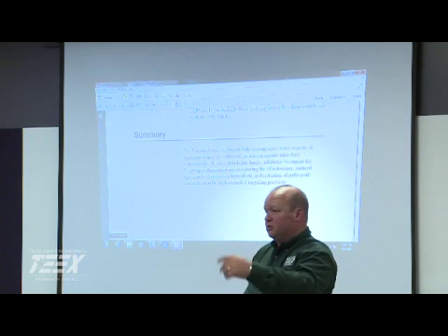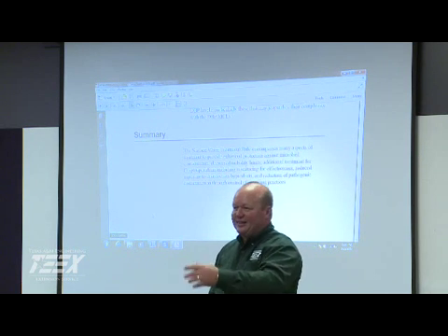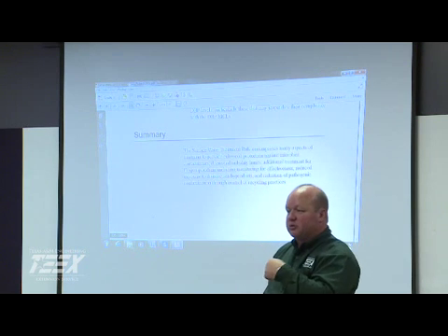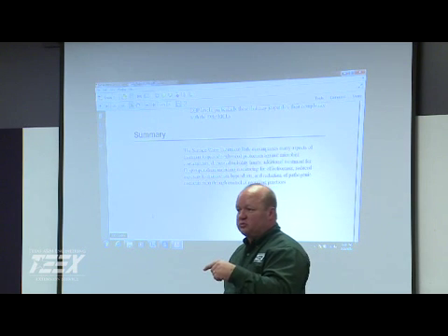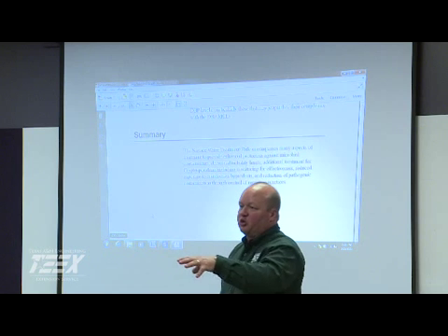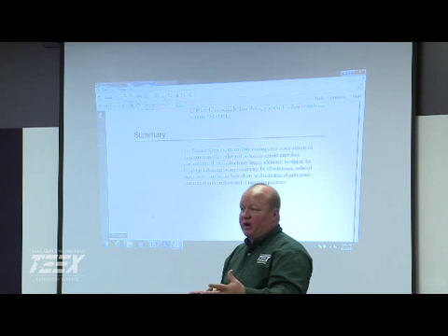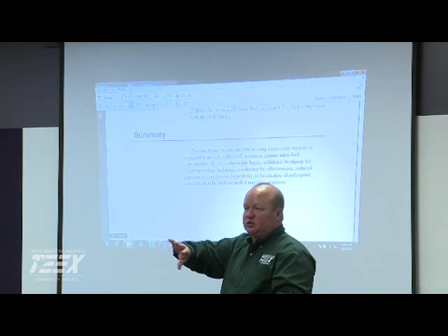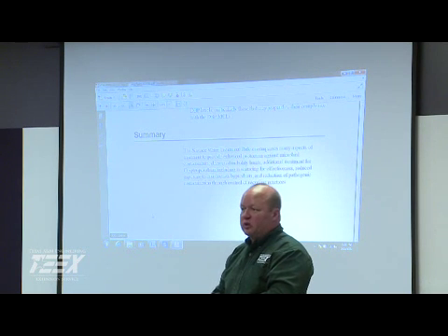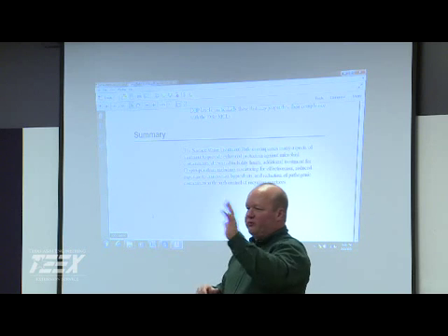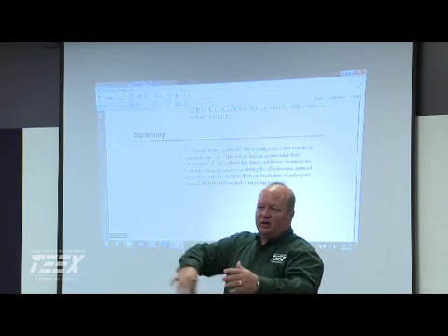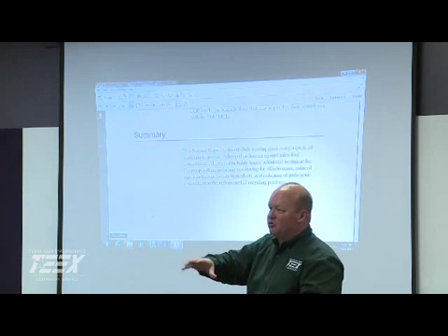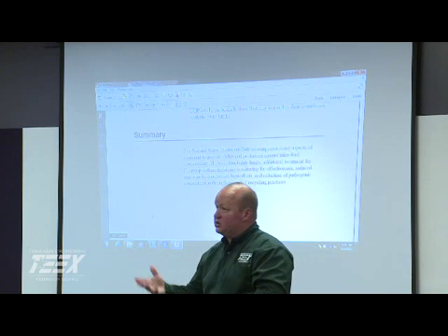And valving, valving is a huge issue. When you start looking at the dynamics of your distribution system, where are your dead spots? How can you work your valving to get some of that water to move out of areas that you don't want it sitting for a long time? That's master planning. Because you can be short circuiting. You got a fast track here, the highway, and now you got this over here that's the backcountry road. Nobody's using the water out there that's sitting.